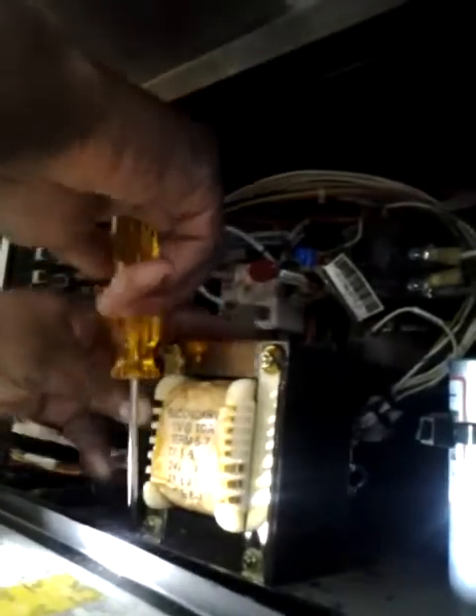Transformer is going to go back in place. These 2 screws will secure it. And this is the type of stuff that you would learn on the job as you start. You would start off as a preventive maintenance technician, and you really wouldn't be doing a lot of repairs to start with, but you would be working with these things. You would be taking voltage readings in here. You would check these capacitors with a capacitor meter, and as you go on, you would become a T1 level technician, where you would end up doing compressor changes and contactor changes and stuff like that. So now we're about ready.